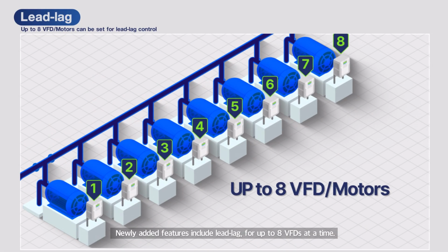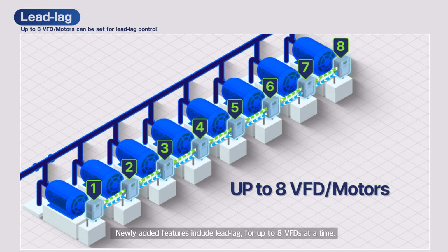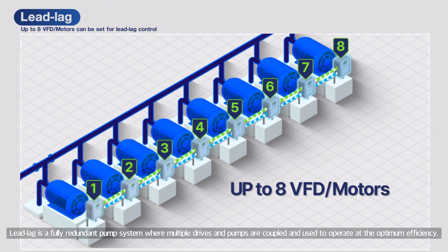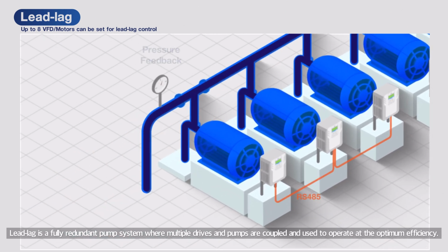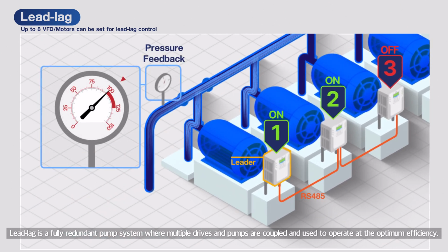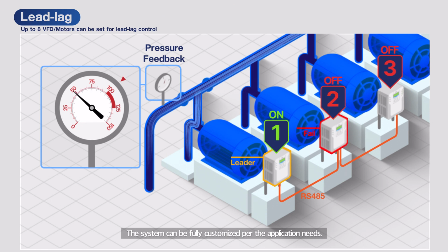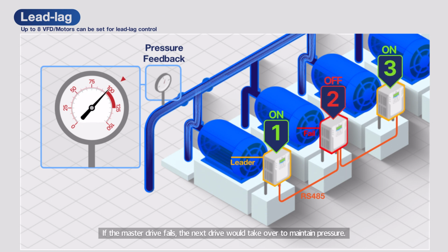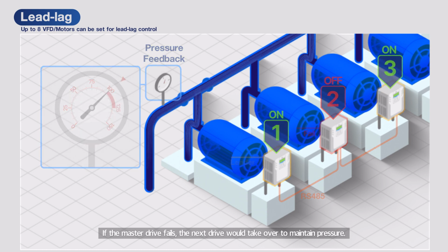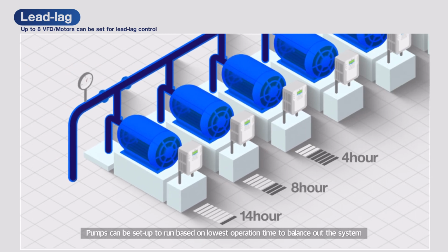Newly added features include lead lag for up to 8 VFDs at a time. Lead lag is a fully redundant pump system where multiple drives and pumps are coupled and used to operate at optimum efficiency. The system can be fully customized per the application needs. If the master drive fails, the next drive would take over to maintain pressure. Pumps can be set up to run based on lowest operation time to balance out the system.